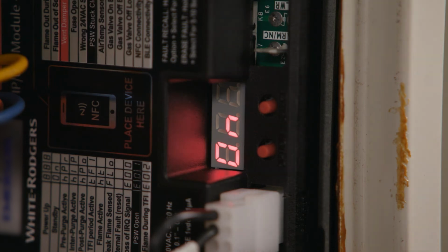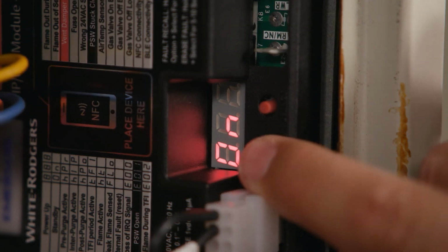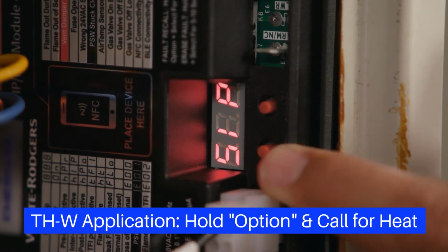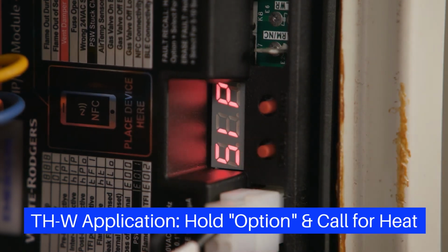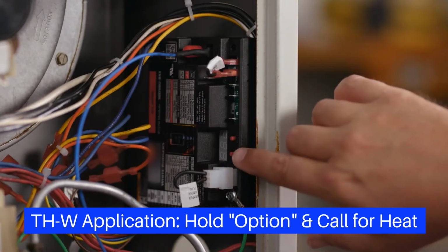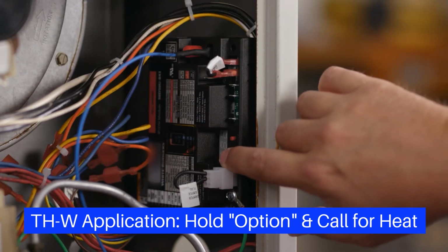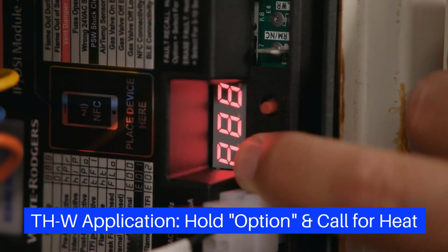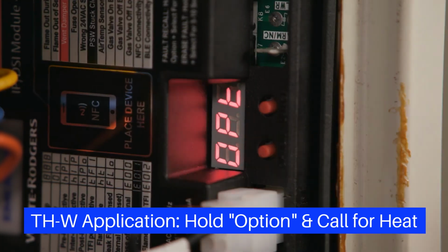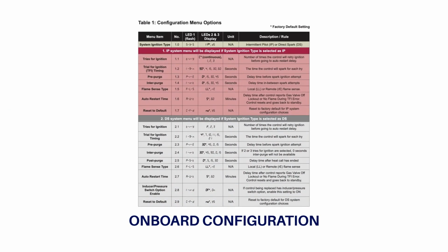To enter configuration, press the Option button while the unit is in standby. For applications that have power only to THW, there is no standby mode. To enter the configuration mode, hold the Option button for 3 seconds while simultaneously supplying 24-volt to THW. Table 1 on page 3 of the installation instructions shows configuration options.